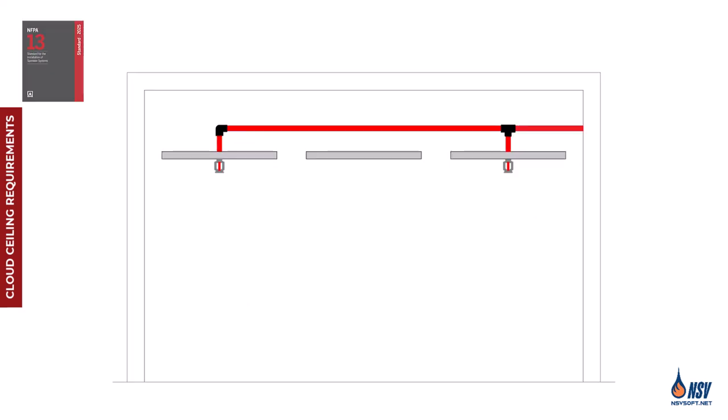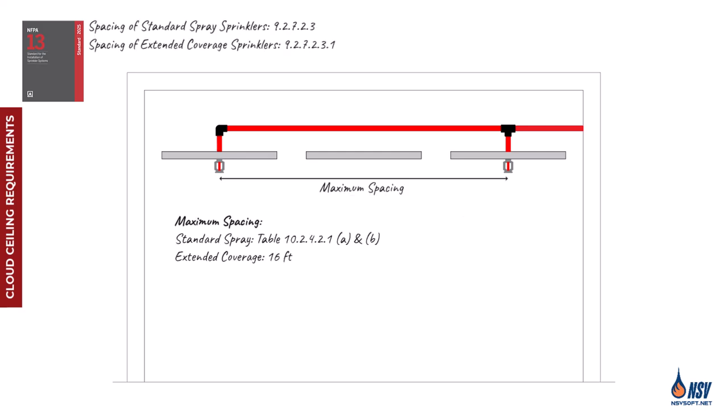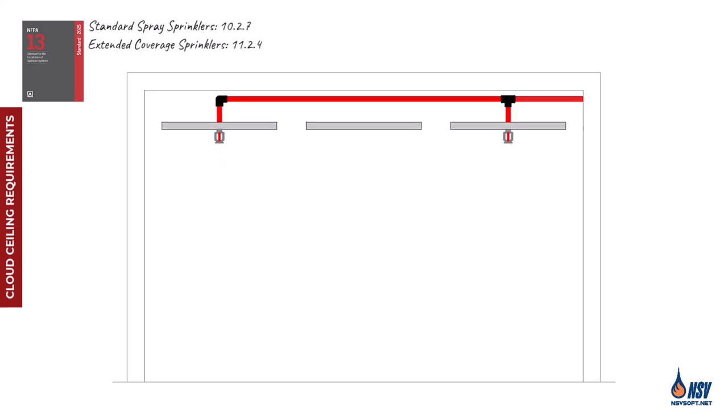Before we wrap up this section, let's review a few remaining requirements. NFPA 13 mandates that quick response sprinklers be used beneath cloud ceilings. If standard spray sprinklers are applied, their maximum spacing must conform to the limits specified in tables 102421A and B. For extended coverage sprinklers, the spacing must not exceed 16 feet. And finally, perhaps most importantly, if the distance from the sprinkler deflector to the structural ceiling remains within the allowable limits, the sprinkler may be installed below the cloud ceiling regardless of whether that ceiling meets other cloud-specific criteria. In such cases, there is no need to install a sprinkler above the cloud ceiling.